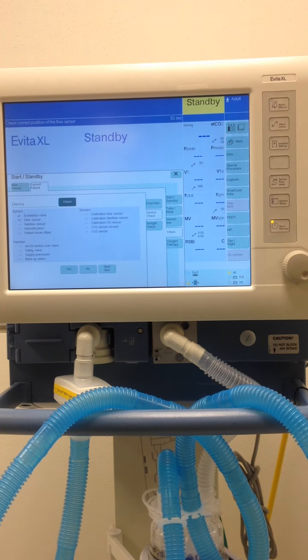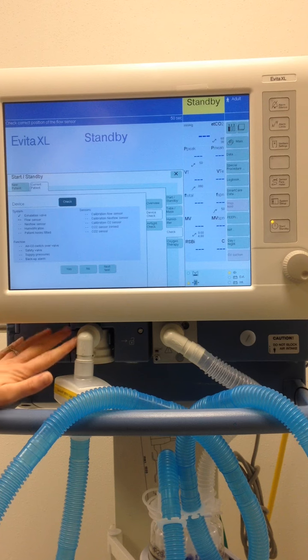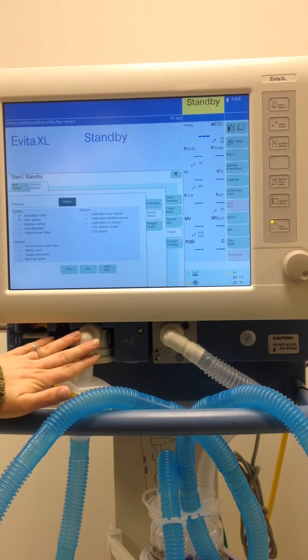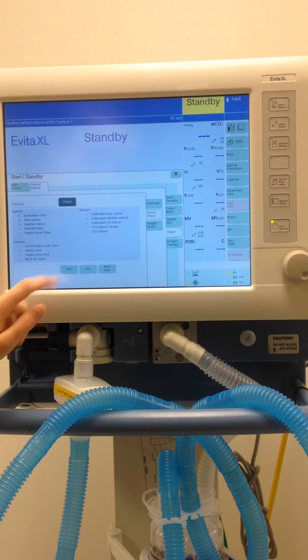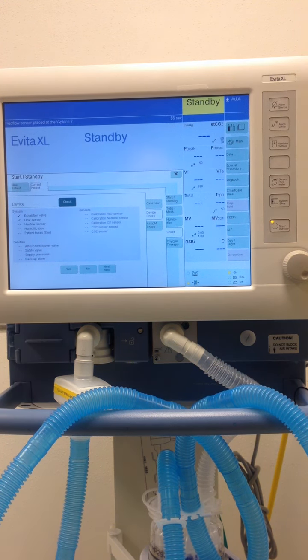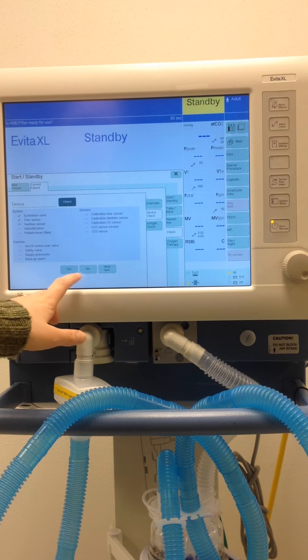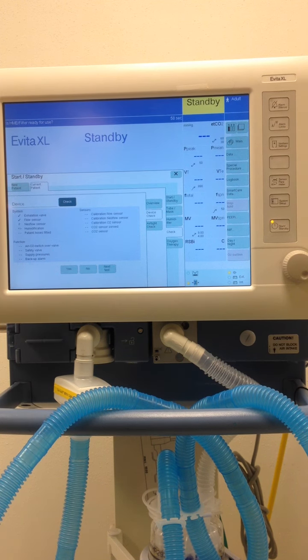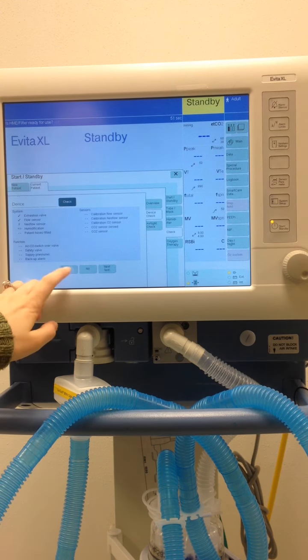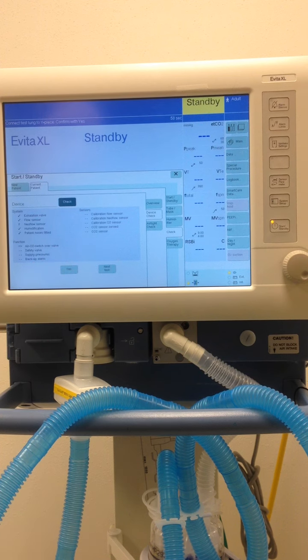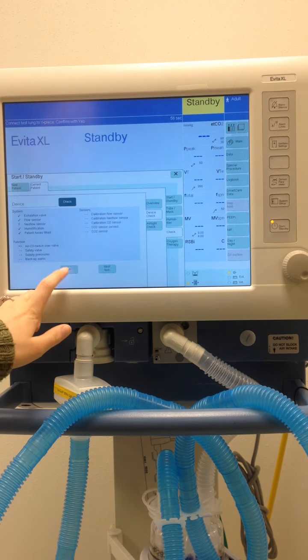And then check correct position of the flow sensor. So we just checked both of these so we know that they're okay. So we can click yes. Neo flow sensor placed at the Y piece. We're going to check no on this one because we're doing an adult circuit. Is the HME filter ready for use? We can say yes because we're not using an HME, but we are using the Fisher-Paykel heater. Connect test lung to Y piece and confirm with yes.